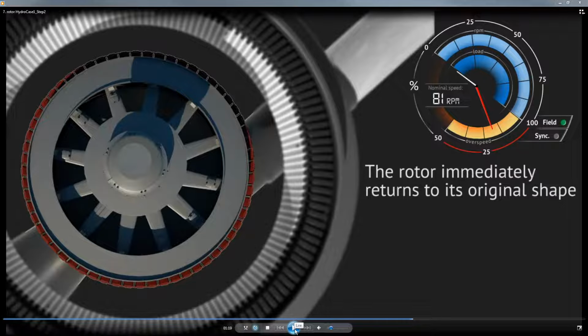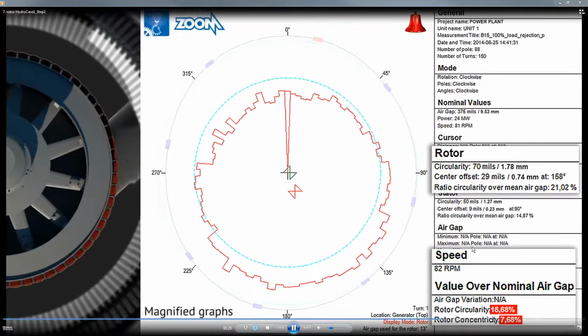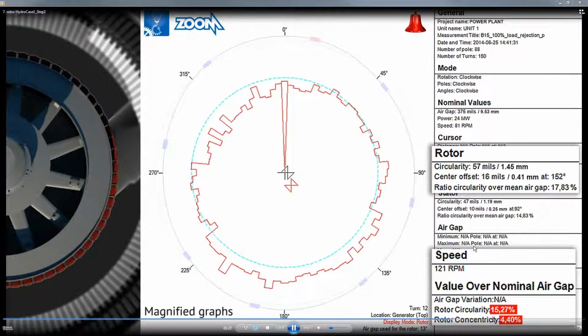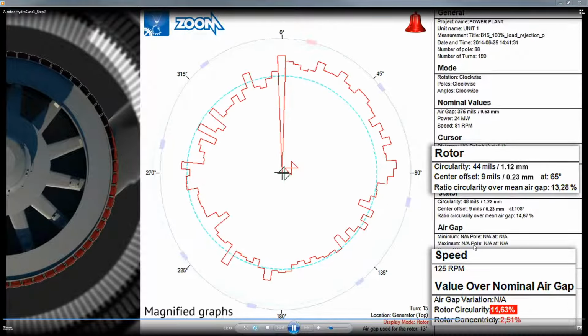But the problem is that without any field, it doesn't produce a lot of power. So it doesn't produce a lot of money. You're not really interested in what the shape is when the unit's not producing any money. You're interested in what the shape and the performance are when the unit is actually producing power. I had seen issues with load rejection measurements before, but synchronization effects, I had never seen that before.